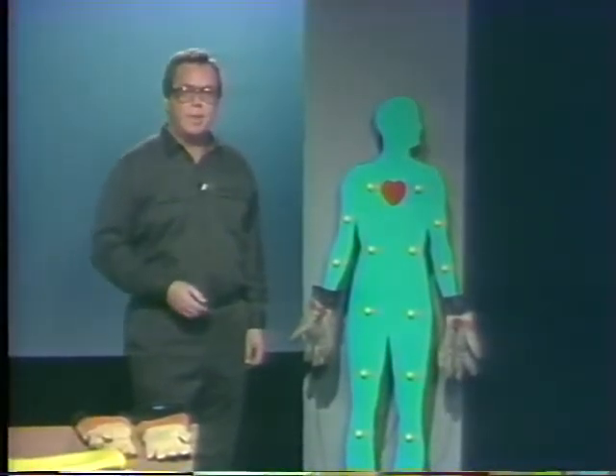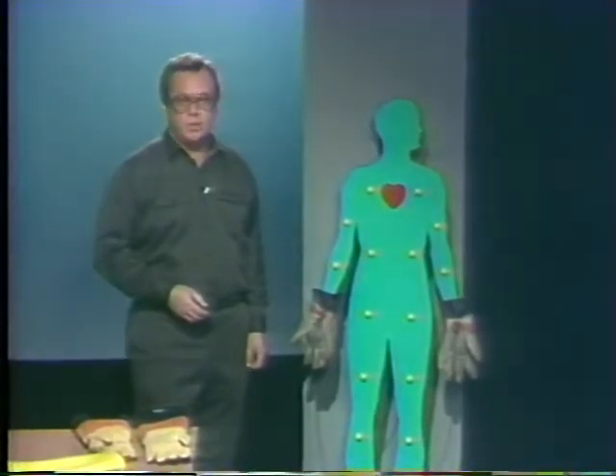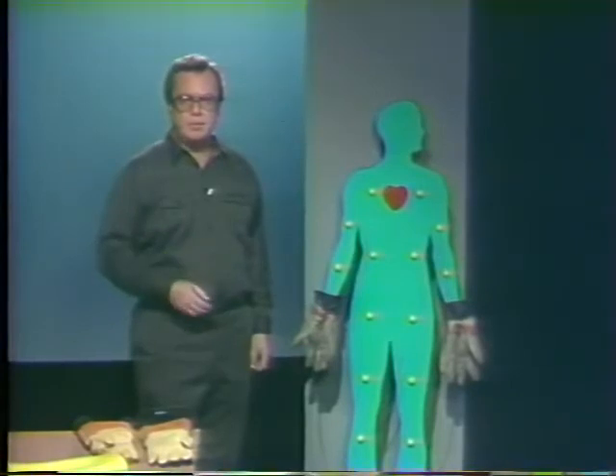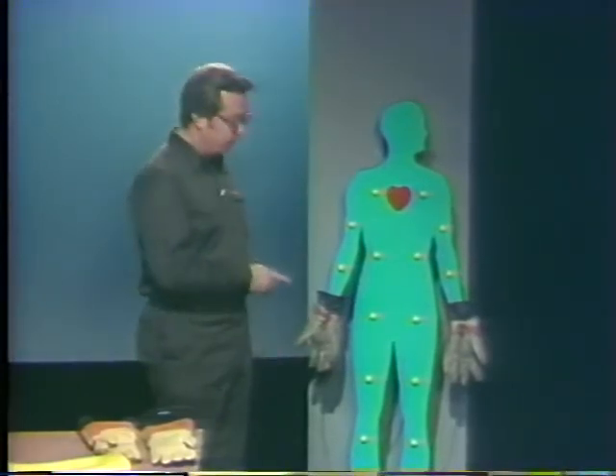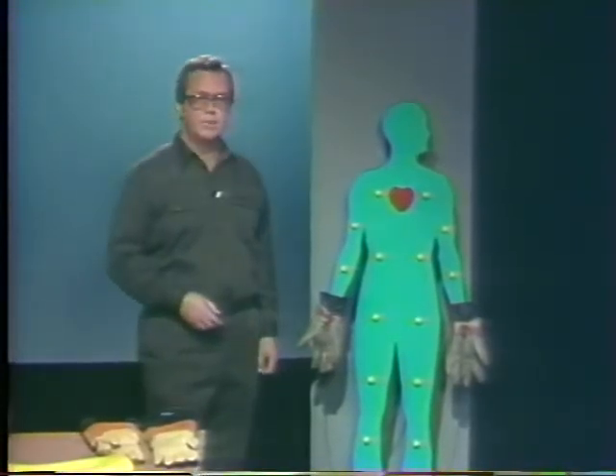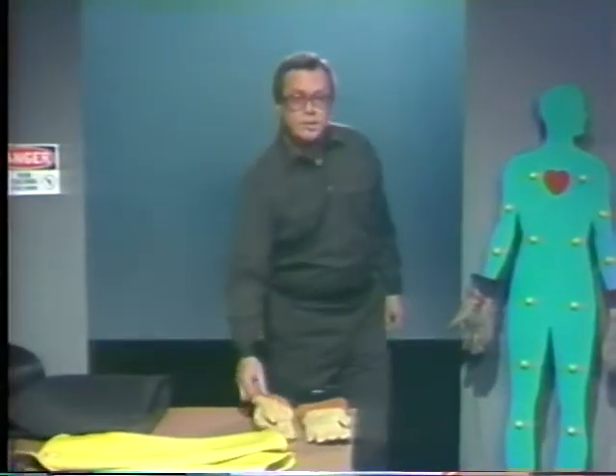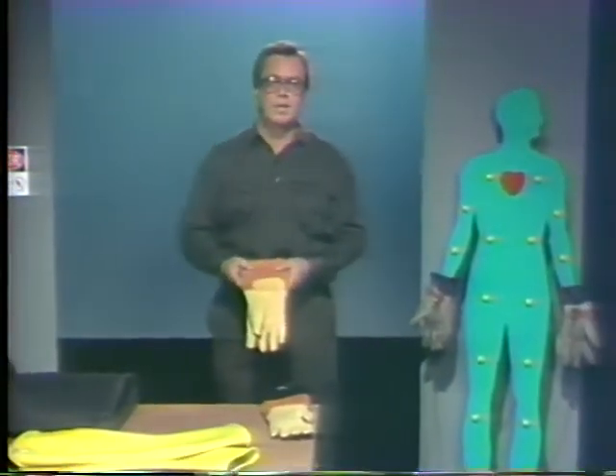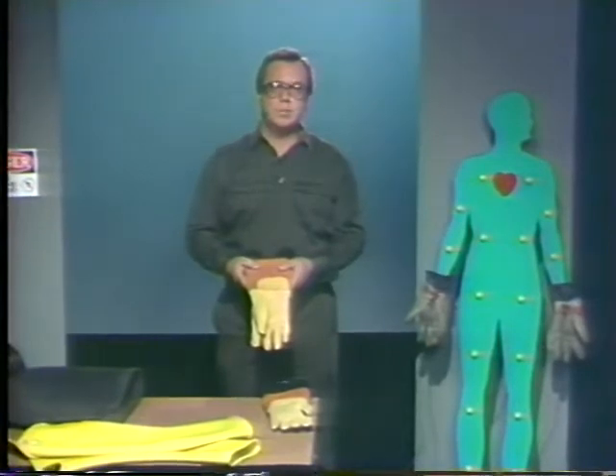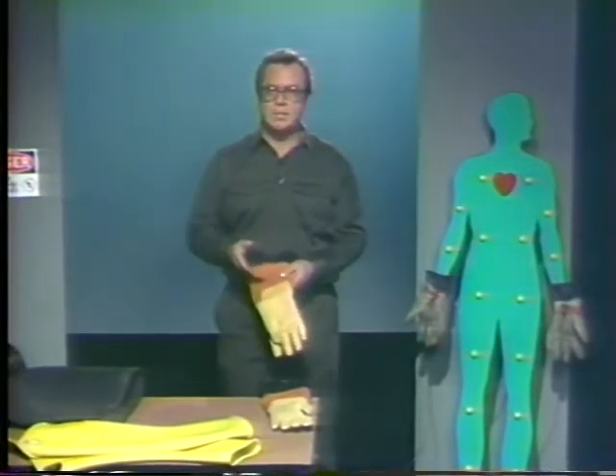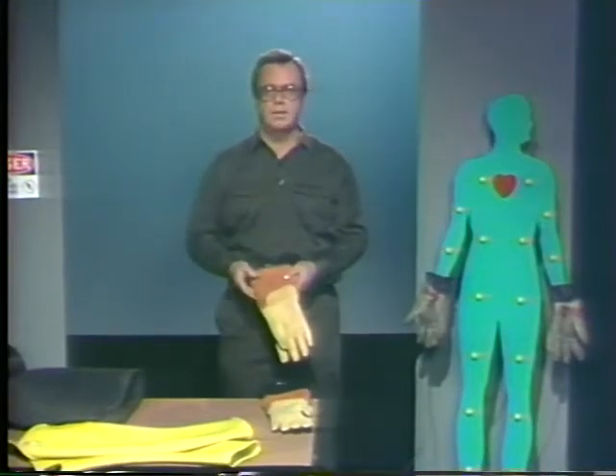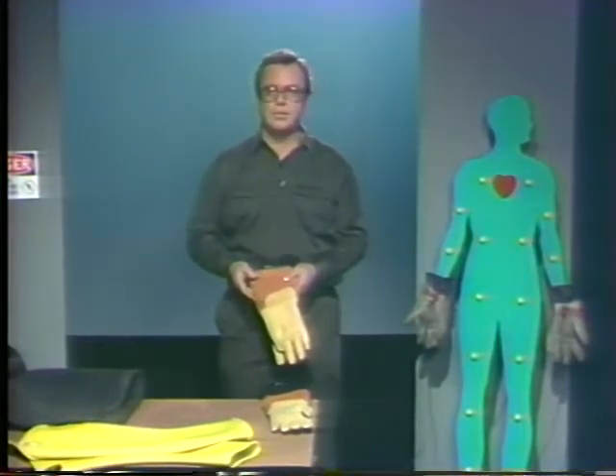Your plant safety manual will tell you when you're required to wear gloves and what type of gloves to wear. We have two examples here. The gloves on the electrical man are rated at 600 volts, but these are rated to 20,000. If your hands are going to be near an exposed hot conductor, you have to have a glove rated for at least as much voltage as that conductor's carrying. And it's a good idea to have a safety margin as well.